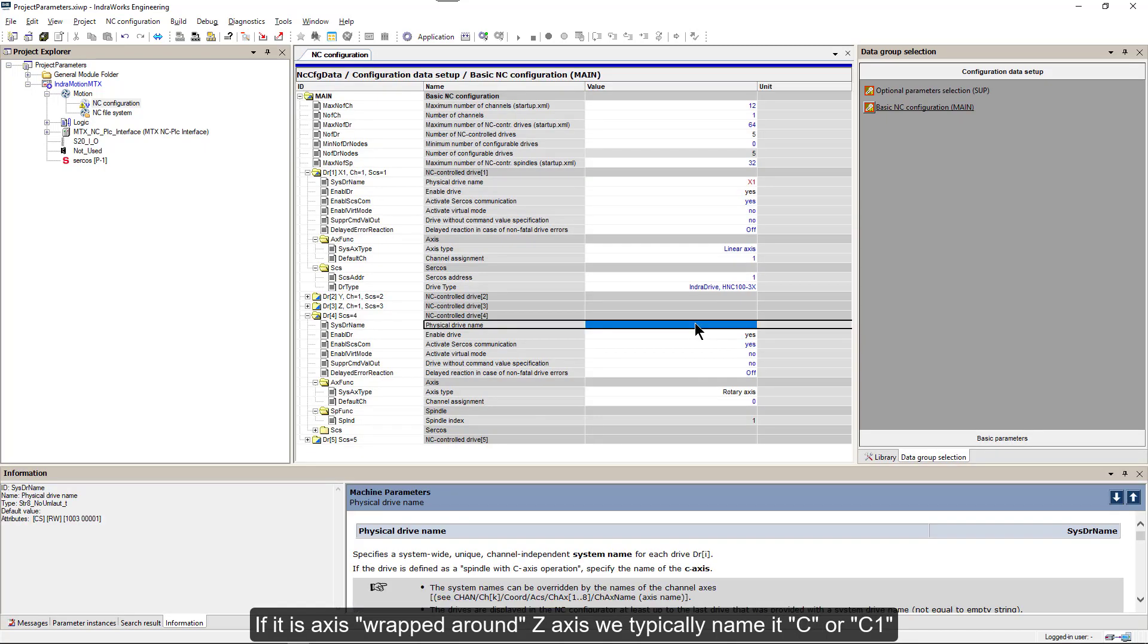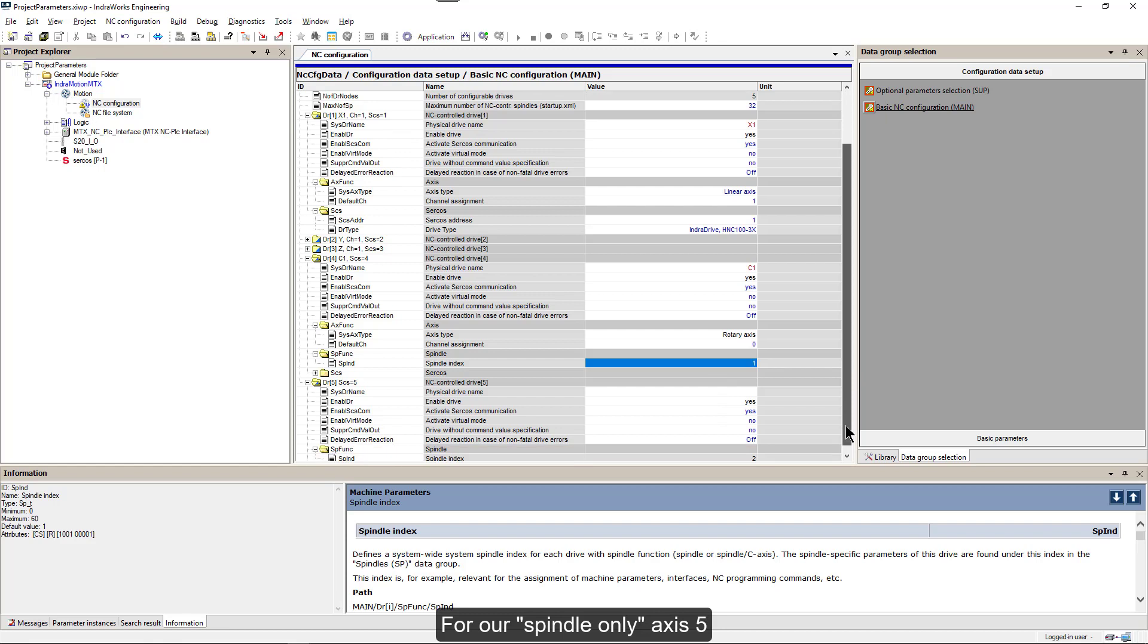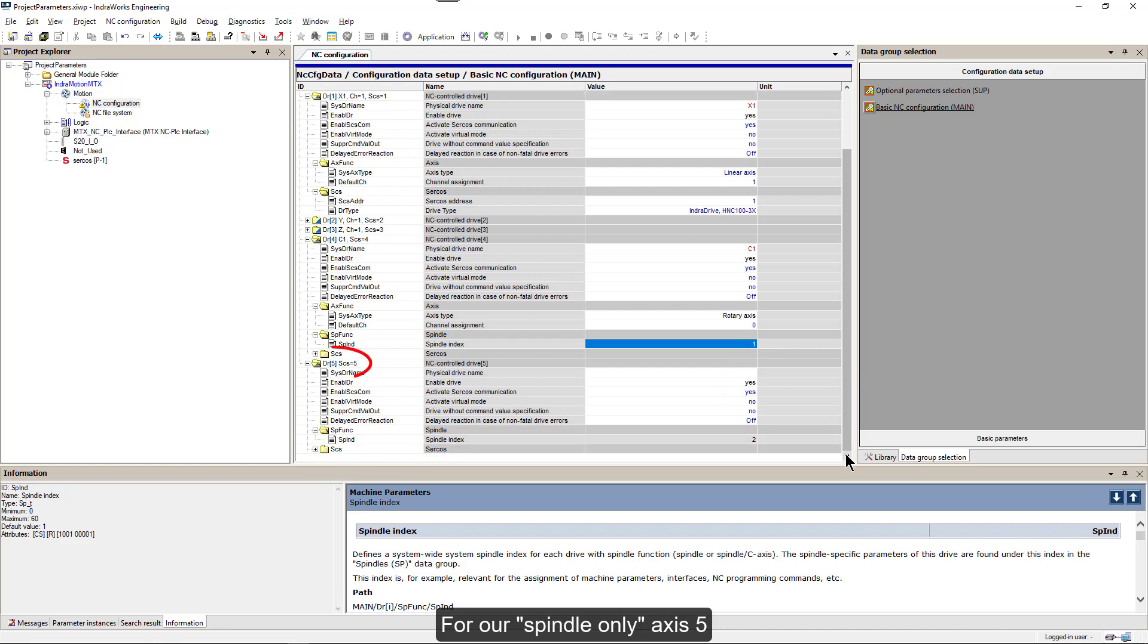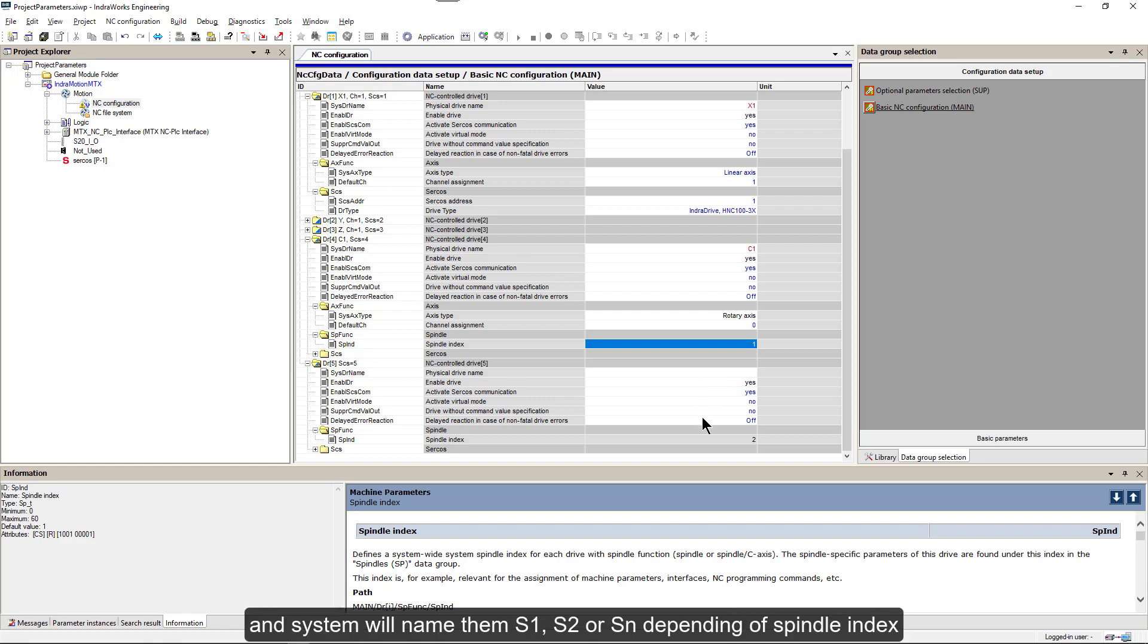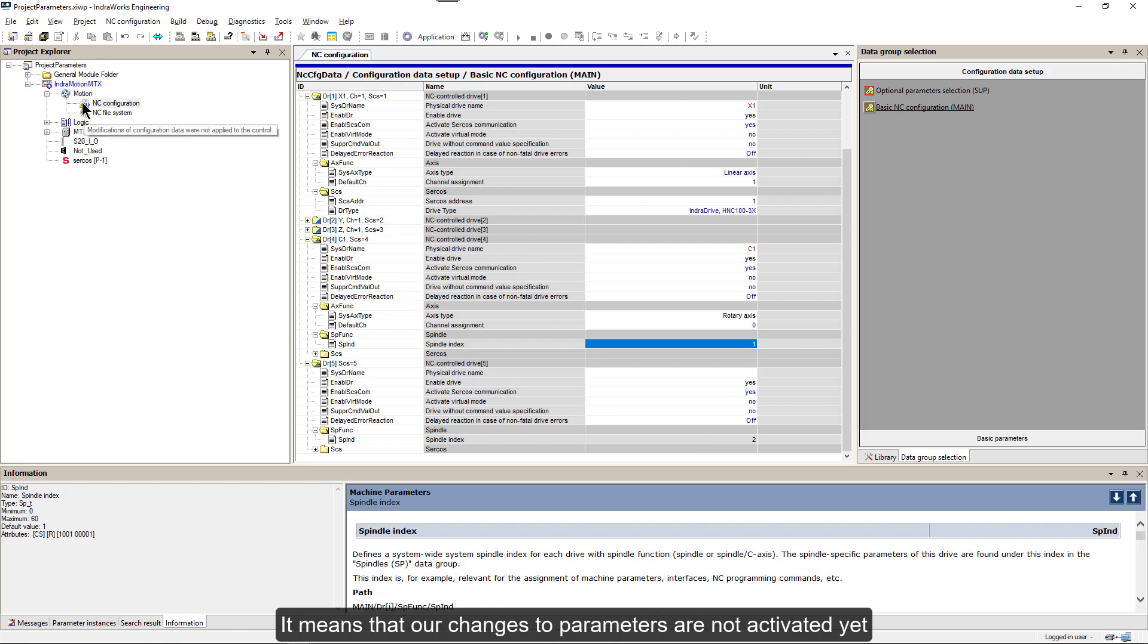If it is Axis wrapped around Z-Axis, we typically name it C or C1. For our spindle only Axis, we do not need to assign a name. And system will name them S1, S2 or Sn depending on spindle index. Please note small yellow warning sign next to our NC configuration tab. It means that our changes to parameters are not activated yet.